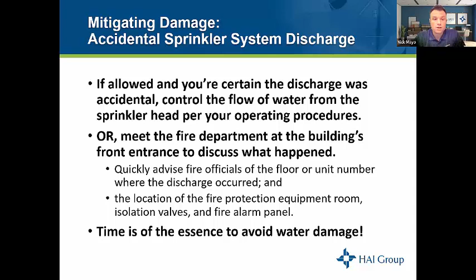In talking about sprinkler systems, and I've already touched on this in the earlier parts of the presentation, sprinkler systems will have isolation valves. They're primarily used to control or isolate portions of a building's sprinkler system. So valves, if they are there, need to be labeled and identified. As I said before, we need to be aware that upon closing an isolation valve, a particular zone of that sprinkler system will be inoperable. So if we are able to locate and use an isolation valve to isolate a portion of the sprinkler system due to an accidental discharge, then we can shut down that particular zone and the rest of the sprinkler system stays in service.